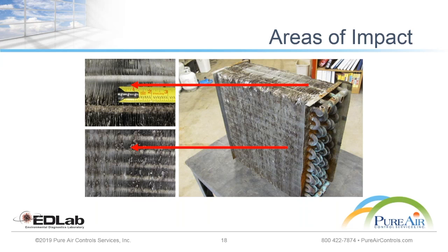On the flip side of that, if you're operating under deferred maintenance, you're trying to stretch your filter changes out, your filters get dirty, guess what? That causes resistance, that puts negative pressure into the air handler unit, and now any place that air can flow besides the filter is going to become a slipstream for these allergens to get into the coil and then be blown through the rest of the building.